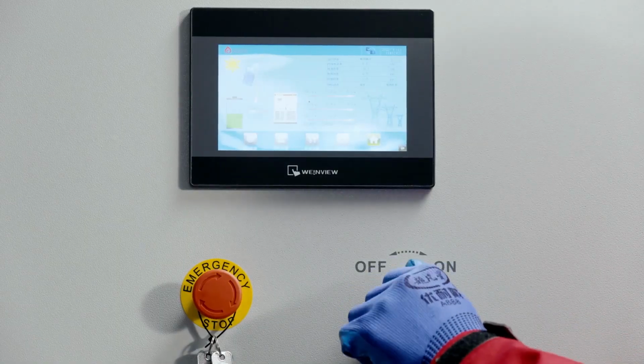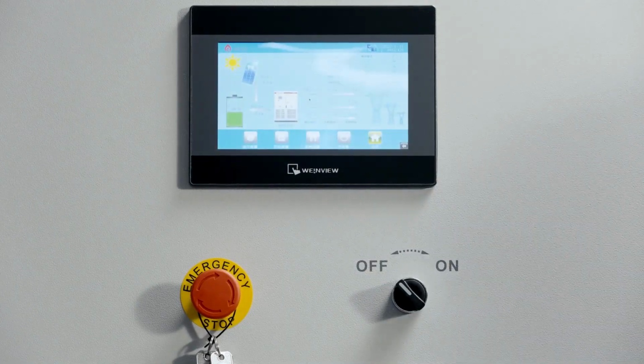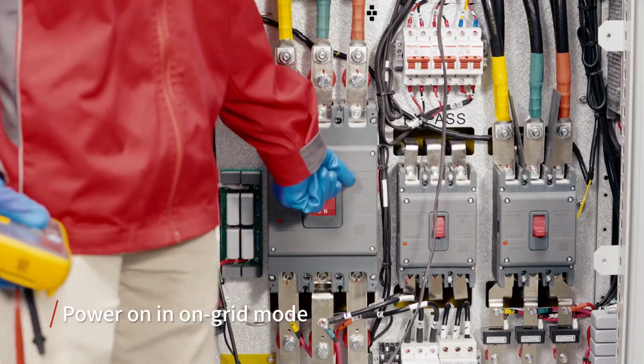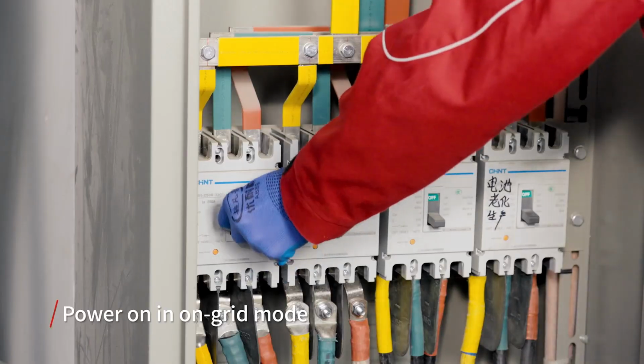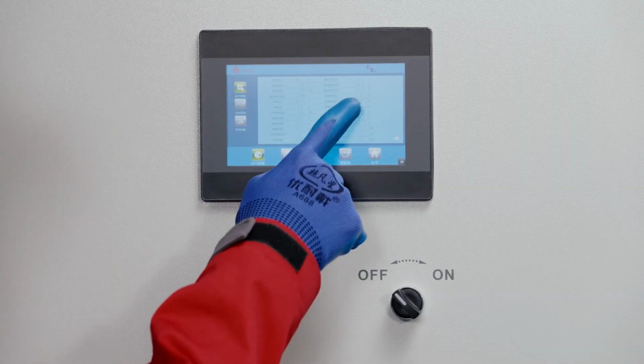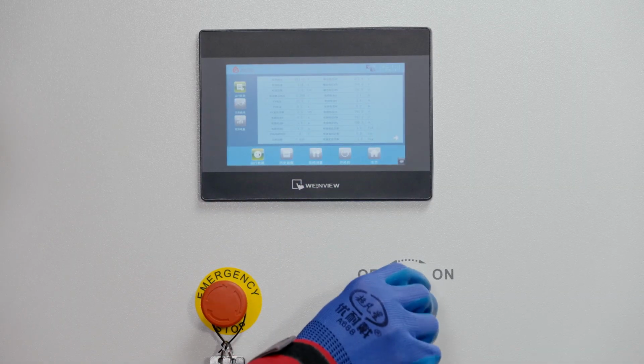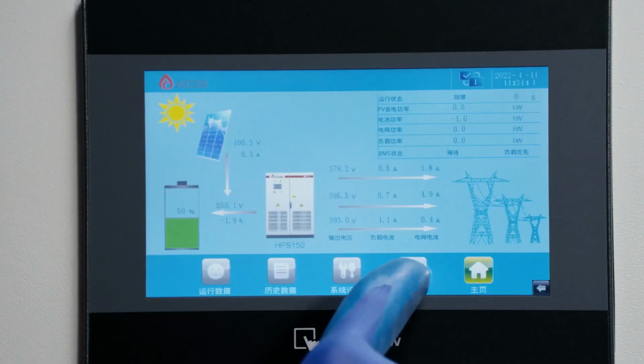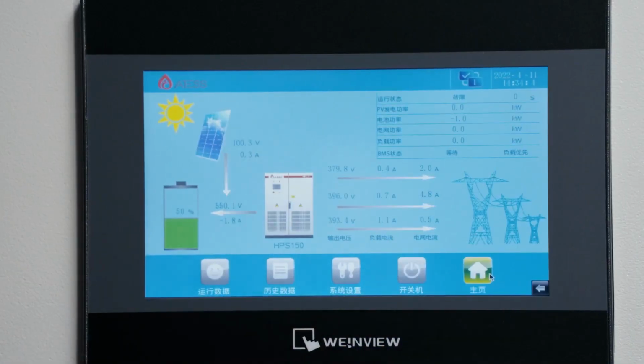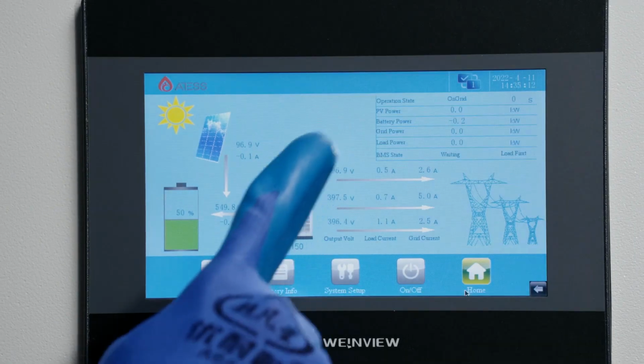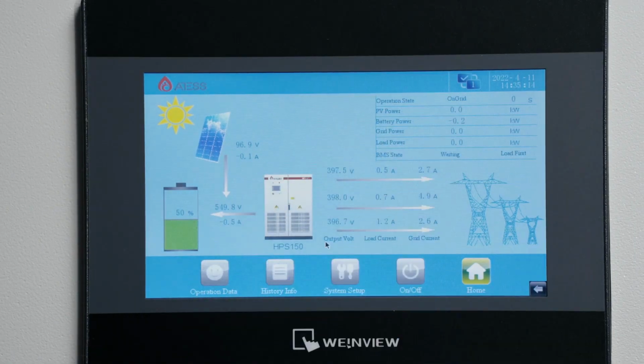After off-grid mode works well, turn the black knob to off. Turn on the grid breaker of HPS and then the external grid breaker. Check if the grid voltage displayed on the screen is correct. Turn the black knob first and then click the on button on the screen. Check if the running data on the home page is normal.